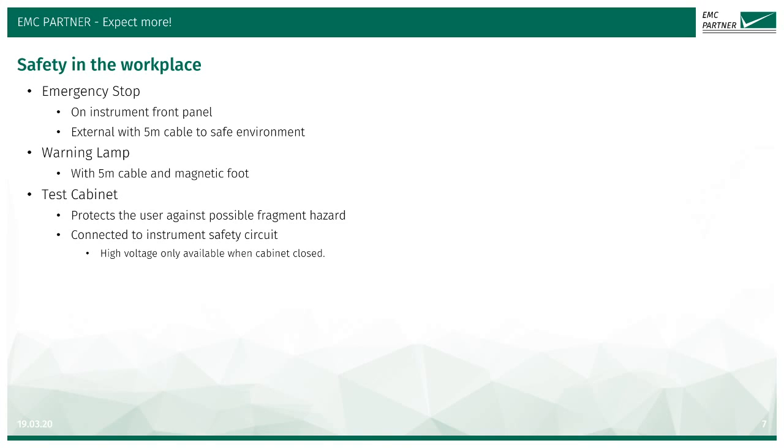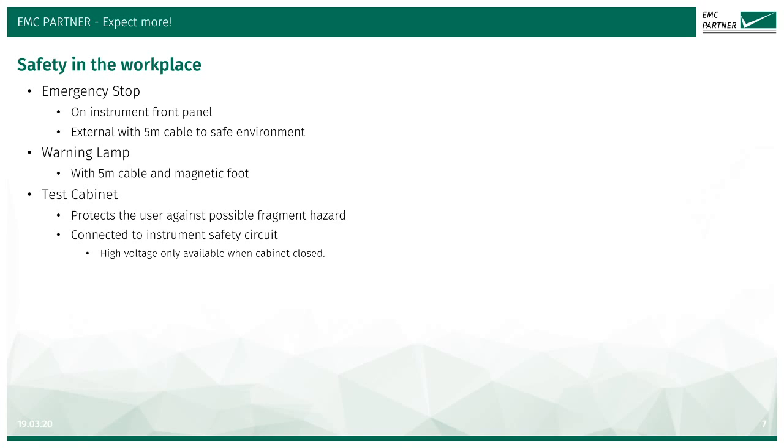A warning lamp connected to the instrument indicates when the high voltage circuits are active. When the high voltage circuits are deactivated, the warning lamp is green and the test object can be manipulated. A test cabinet is provided to protect the user against a possible fragmentation hazard should an EUT explode unexpectedly. The test cabinet is connected to the instrument safety circuit, so that when the high voltage is enabled, the test cabinet cannot be opened.